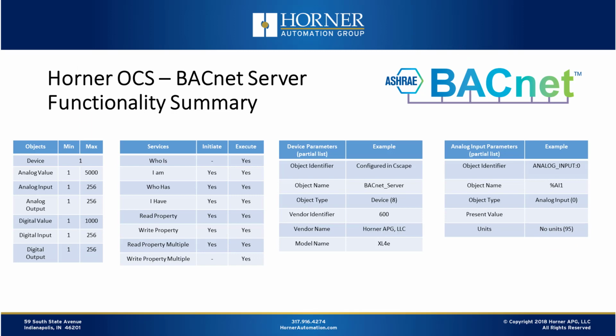Okay, now to summarize the functionality that you'll find in our product as it relates to our BACnet server capability, because remember, we are a BACnet server. We are not managing the entire network. We are not managing a building. We are typically applied as a device in the building, such as a chiller or controlling an air compressor, performing lighting control or lighting automation. Again, we're acting as a server, whereas the building management system is going to typically act as the client.